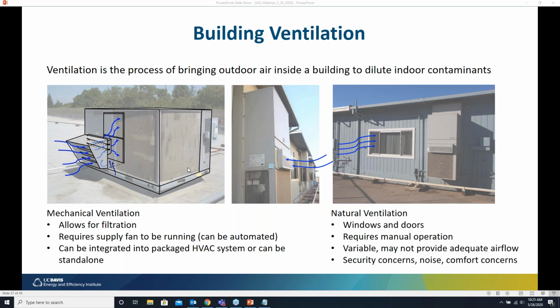Okay, so as Rengie described, we have mechanical ventilation and natural ventilation. I'm going to talk about mechanical ventilation first. The big benefits of mechanical ventilation are that it allows for filtration. It's supplied by a fan, so it can be controlled through an automated system, and it can be integrated into a packaged HVAC system, or it can be standalone. Natural ventilation uses doors and windows. Generally speaking, it requires manually opening them. And it's quite variable depending on weather conditions and may not provide adequate airflow. There are also concerns with security and noise and comfort.